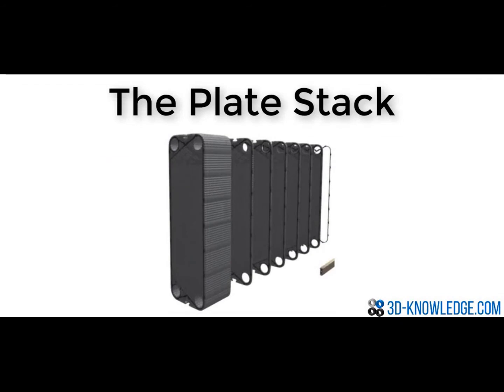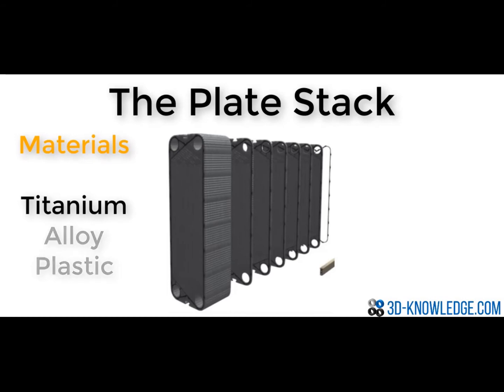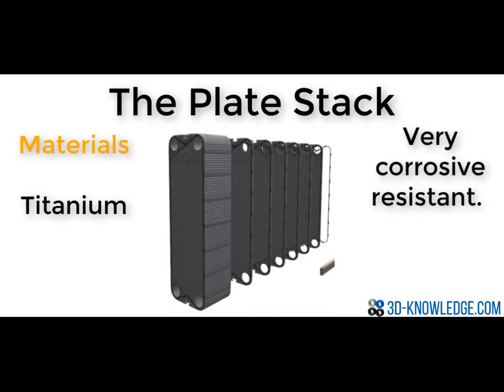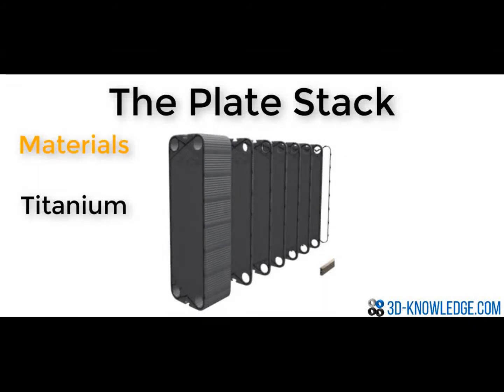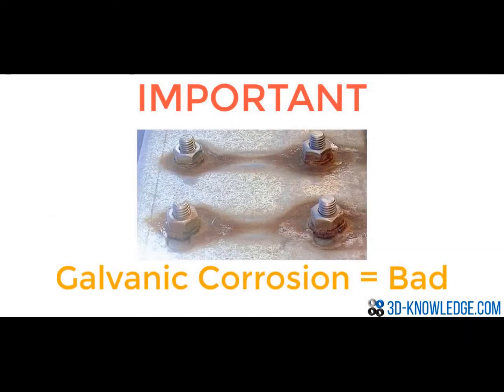The plates themselves can be manufactured from a number of different materials, ranging from titanium to different sorts of alloy, as well as plastics. Titanium would be chosen whenever the environment is particularly corrosive. Titanium has excellent corrosion resistance characteristics, but unfortunately it's incredibly expensive. Another disadvantage when using titanium is that any metal connected to it will normally act as an anode. When two dissimilar metals are connected together, one will be an anode and one will be a cathode. The anode will slowly wear away due to galvanic action. Any metals connected to titanium plates will need to be protected, and this can be achieved by insulating the plate from the dissimilar metal or by installing a cathodic protection system.